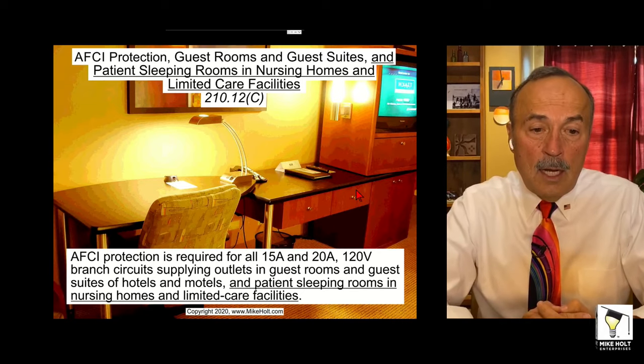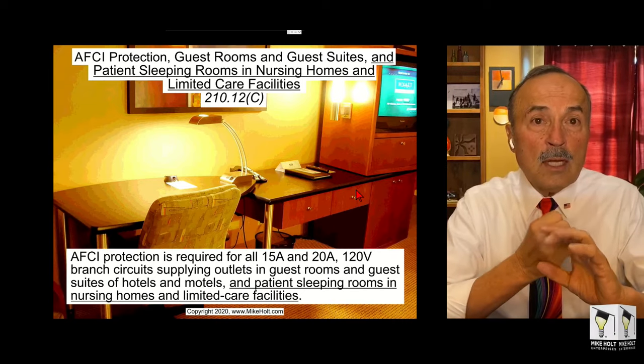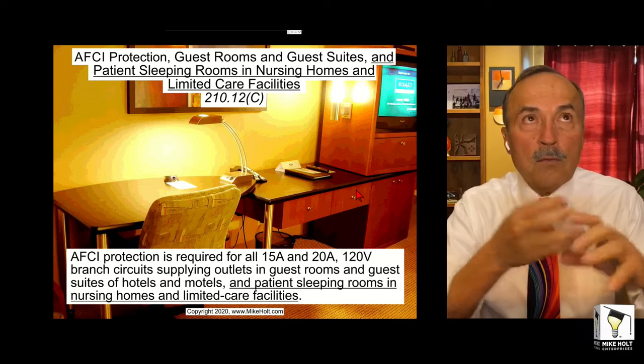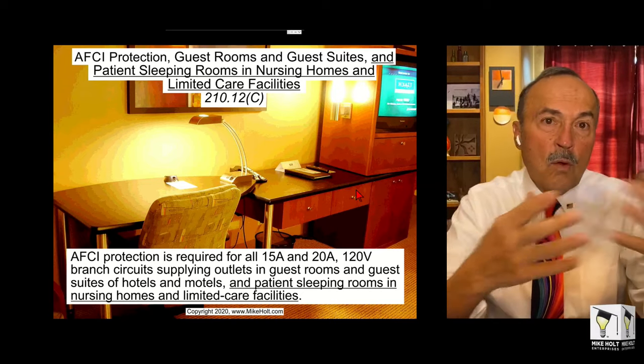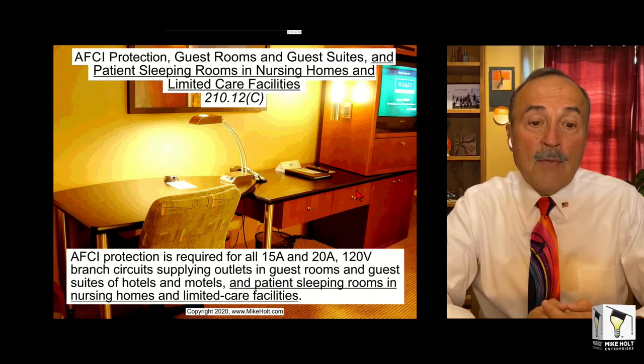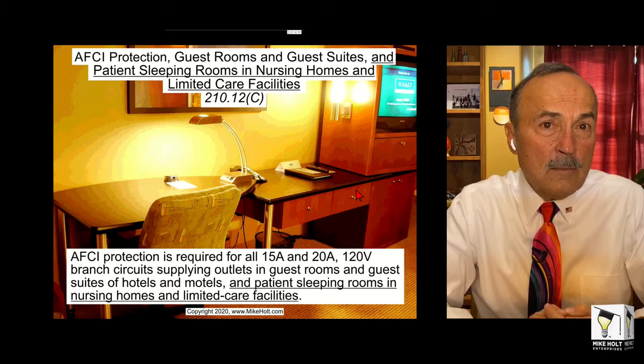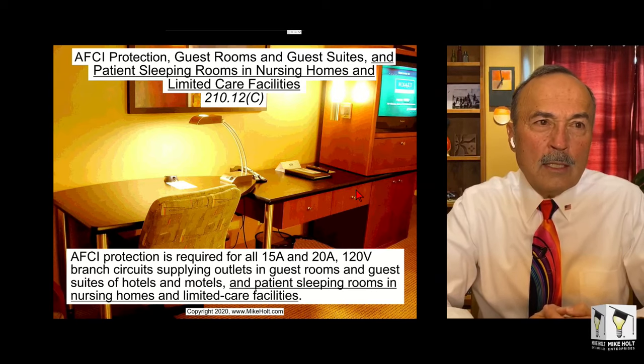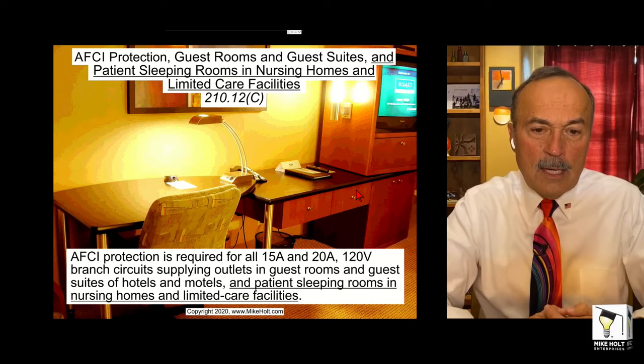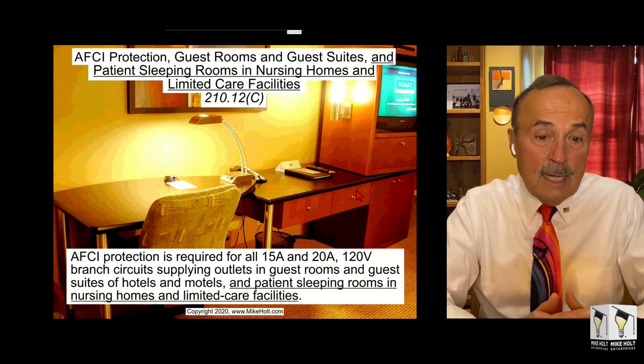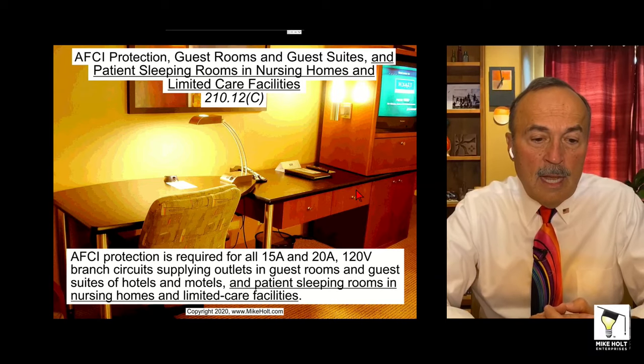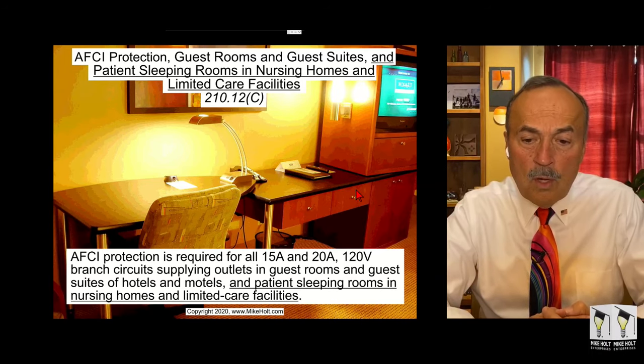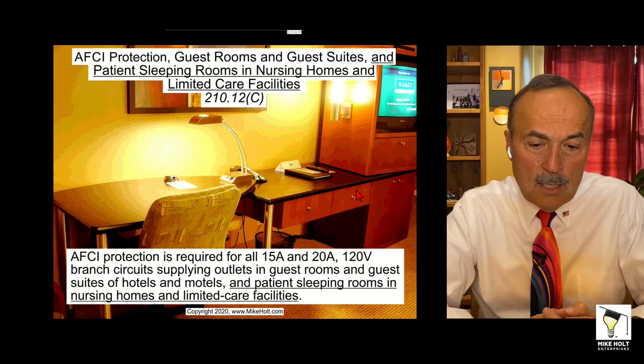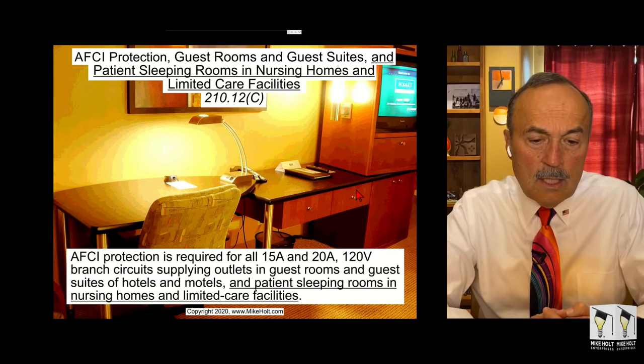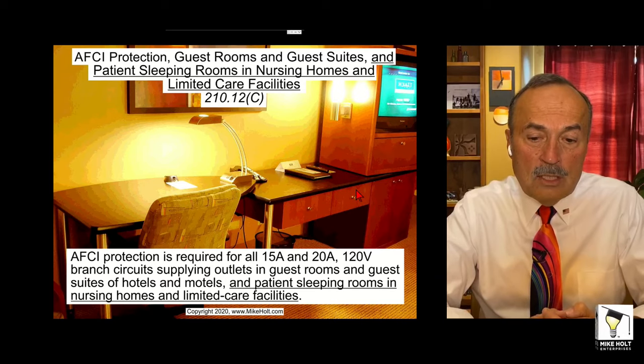Also, they added it, and it's required in guest rooms and guest suites, like a hotel where there's a little living area in the front and then you walk into the bedrooms. That's a guest suite. And they added it to limited care facilities. It's almost like not a nursing home, more like an independent living type case. So let's read the text here. This was a 2020 change. AFCI protection is required for all 15 and 20 amp, 120 volt branch circuits supplying outlets in guest rooms and guest suites of hotels and motels, no change, and patient sleeping rooms in nursing homes and limited care facilities.